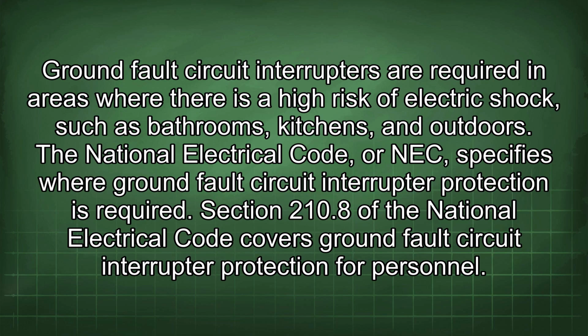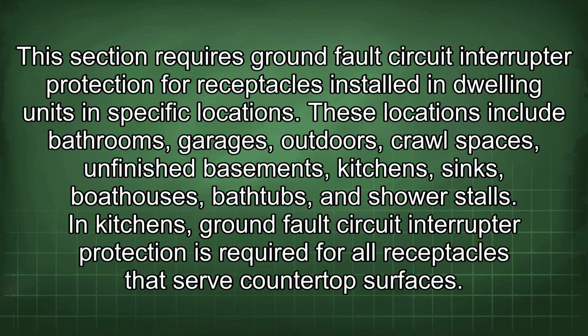Ground fault circuit interrupters are required in areas where there is a high risk of electric shock, such as bathrooms, kitchens, and outdoors. The National Electrical Code, or NEC, specifies where ground fault circuit interrupter protection is required. Section 210.8 of the National Electrical Code covers ground fault circuit interrupter protection for personnel. This section requires ground fault circuit interrupter protection for receptacles installed in dwelling units in specific locations. These locations include bathrooms, garages, outdoors, crawl spaces, unfinished basements, kitchens, sinks, boathouses, bathtubs, and shower stalls.